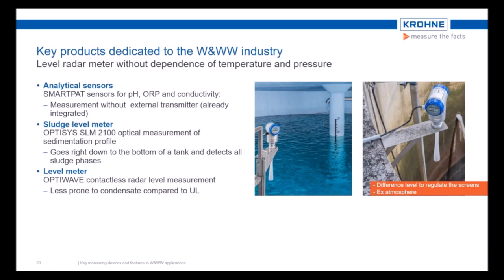Next key measuring device is a level radar meter, which contactlessly measures the level in tanks such as high-level water tanks, shown in the picture on the left, or in open process wastewater basins, shown in the picture on the right. Comparing the radar technology with the previously used ultrasonic level technology, you get significant advantages. So far, normally ultrasonics were used due to the attractive price. Nowadays, almost all suppliers of level measuring technology can offer a basic water radar meter, which is a comparably price-attractive meter.